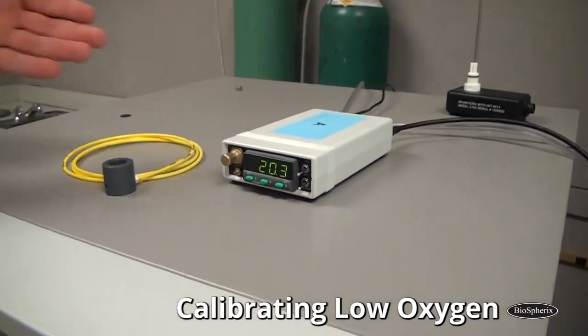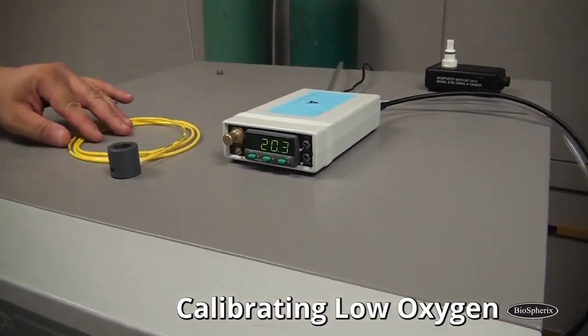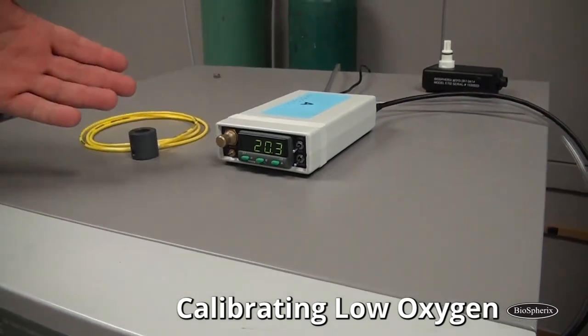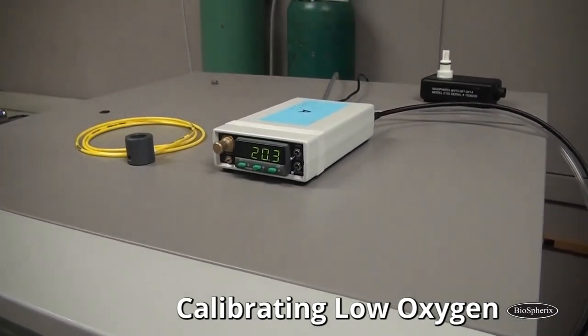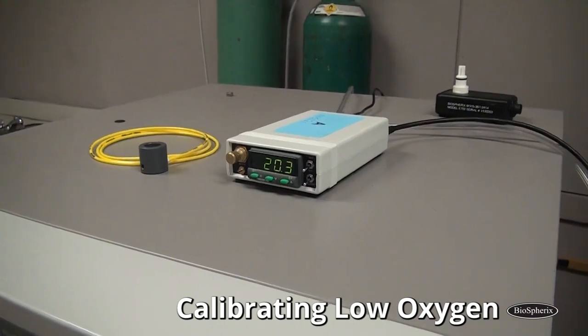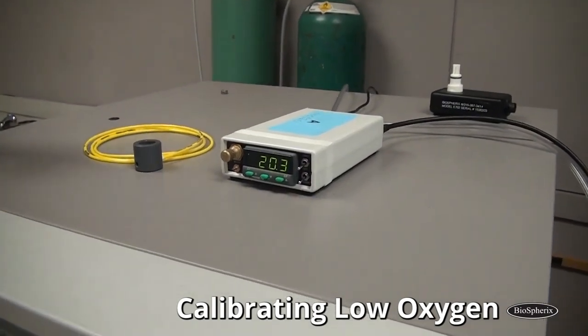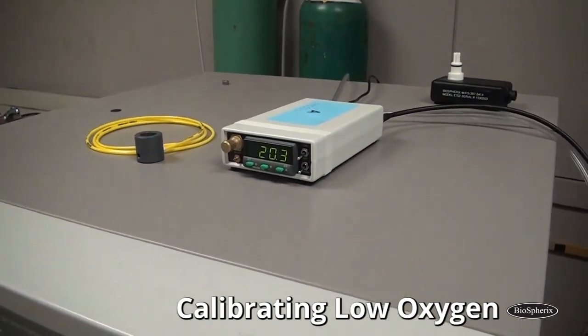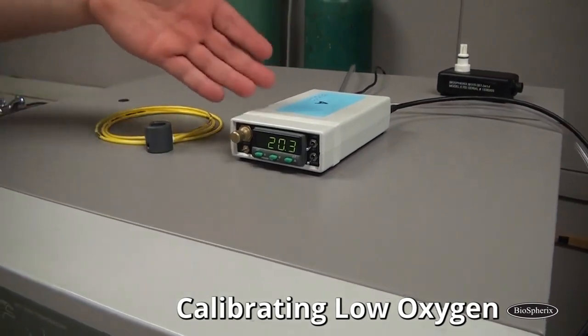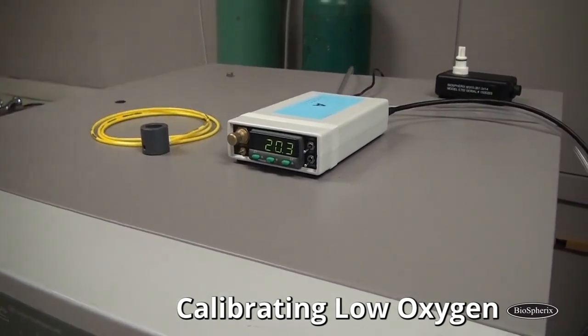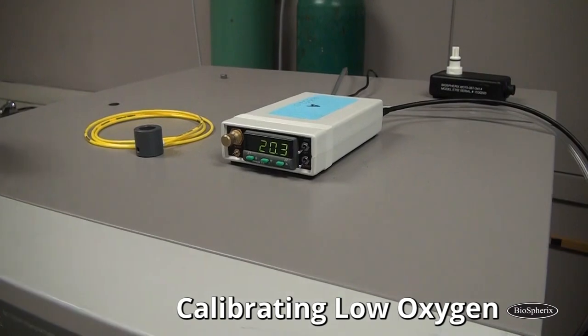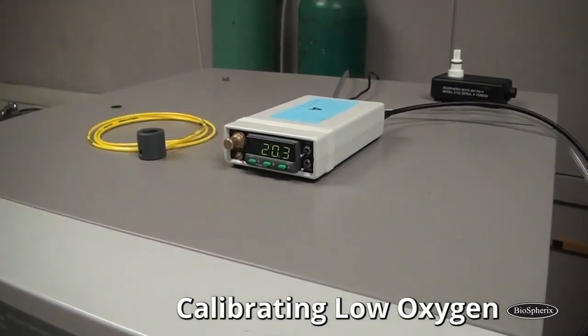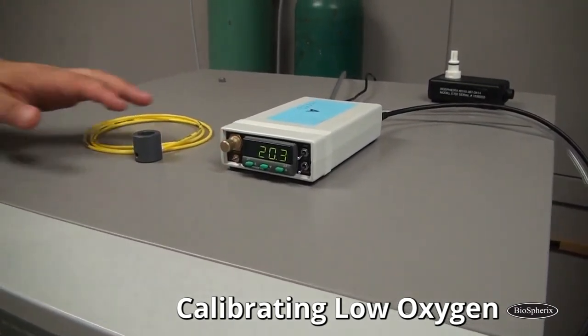And I'm looking at the controller now, and I see it says 20.3. So that's really typical after a couple weeks after calibration. Room air is 20.8. It's a little lower than that inside an incubator when it's all running, but I can already tell it's drifted a little bit. So I want to calibrate. My month is up. My room air reading has drifted a little bit, and I need to calibrate.